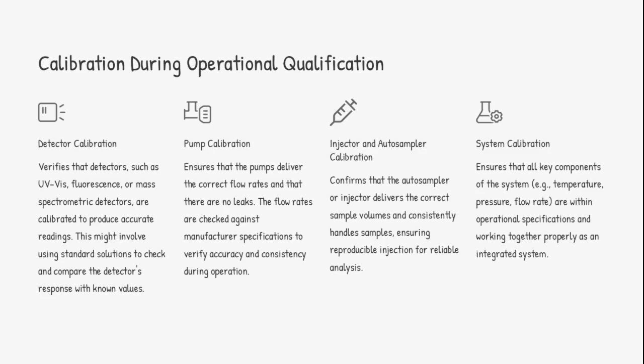Calibration during operational qualification involves verifying that detectors, pumps, injectors, and other key components of the system are calibrated to produce accurate readings. This ensures the system operates with high accuracy and consistency, which is vital for reliable analytical results.